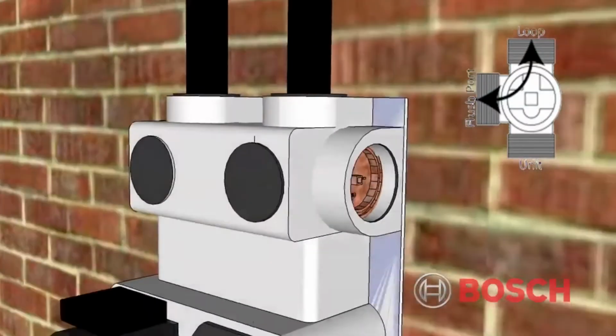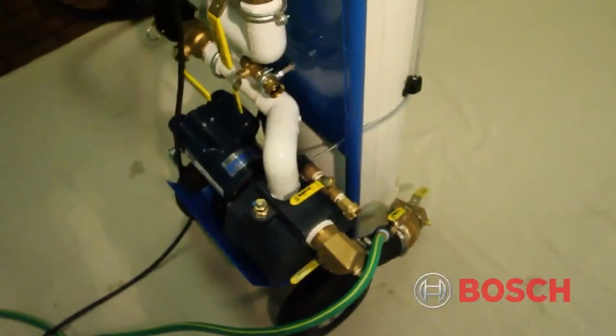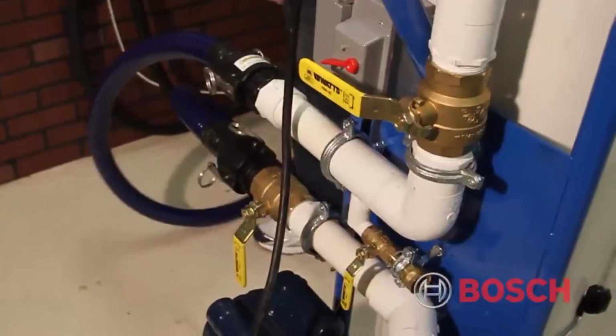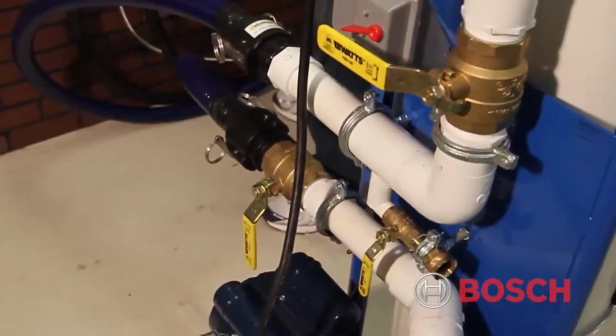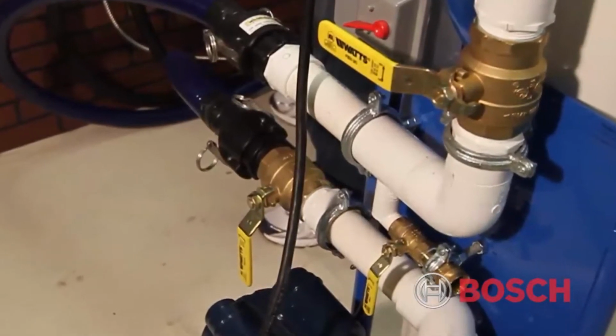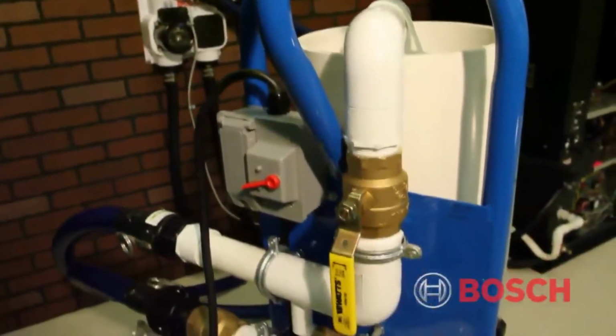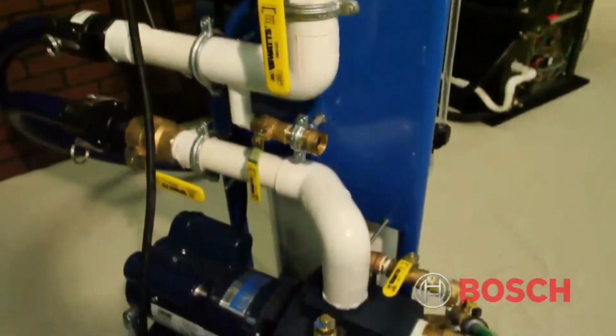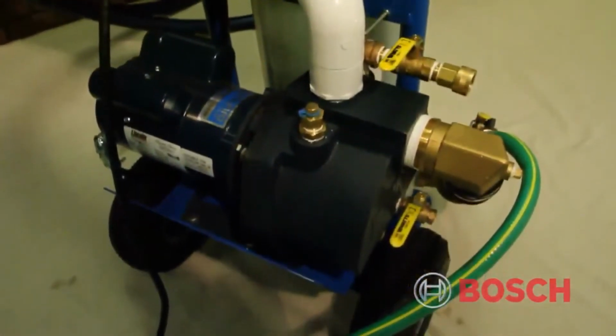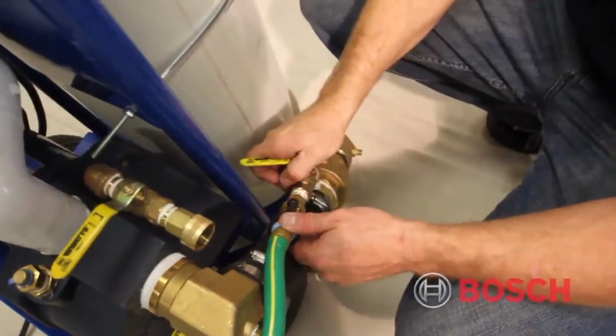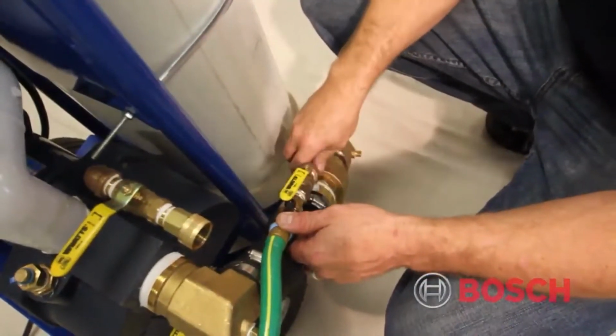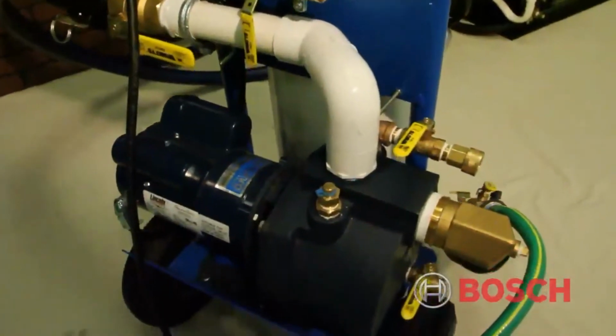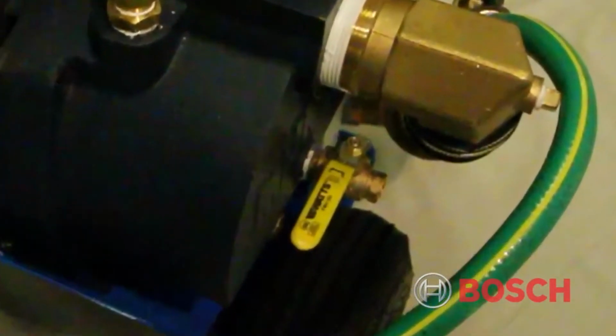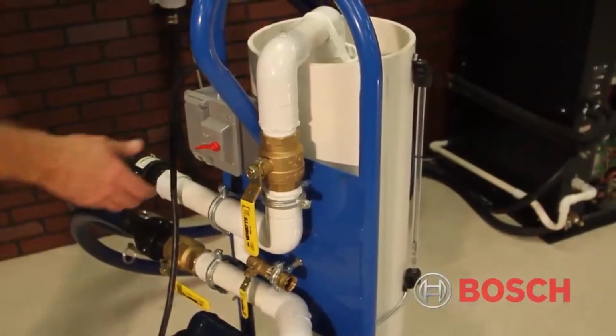Now we need to verify our flush cart is set up properly. Verify the screen filter inside the reservoir is strapped to the PVC return pipe. At this time, all ball valves on the flush cart should be set in the off position. Connect the 20-foot flush cart power cord to a grounded 120 volt 15 amp circuit. Attach garden hose to the GHT swivel adapter on the flush cart. Open up the garden hose ball valve in order to add fluid to the flush cart reservoir. Open up the 1/4-inch pump case drain port valves in order to bleed the air and prime the pump. Flip on the GFI power switch.